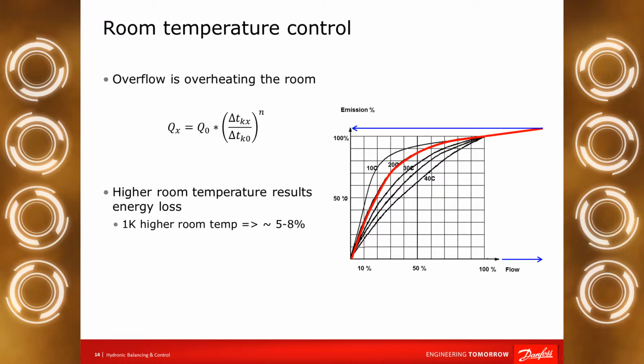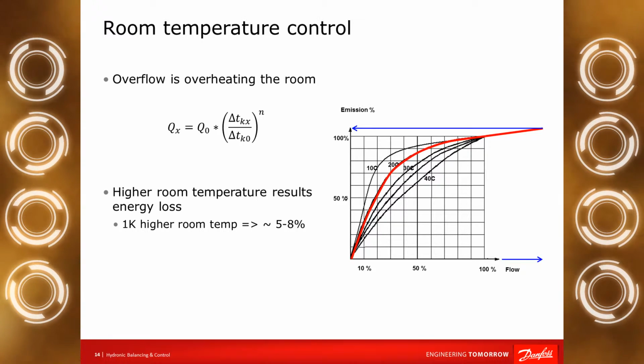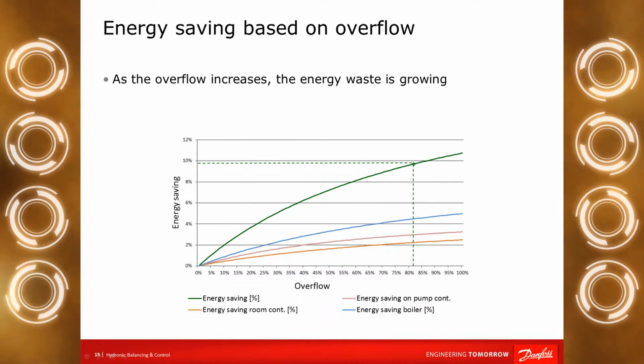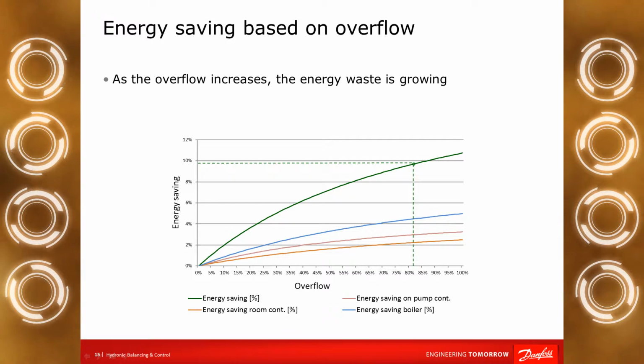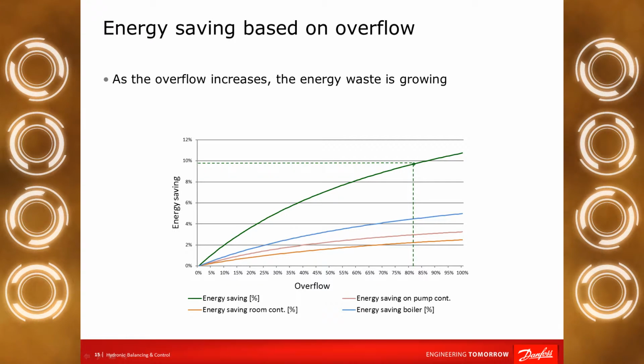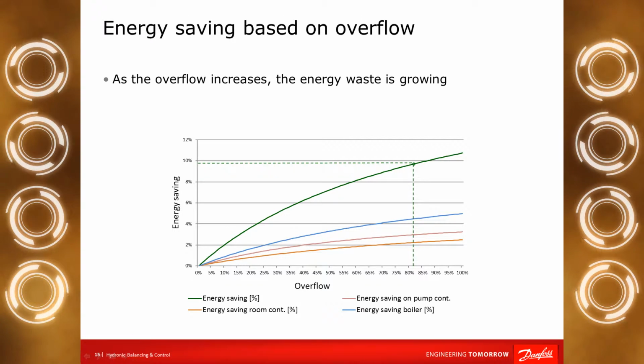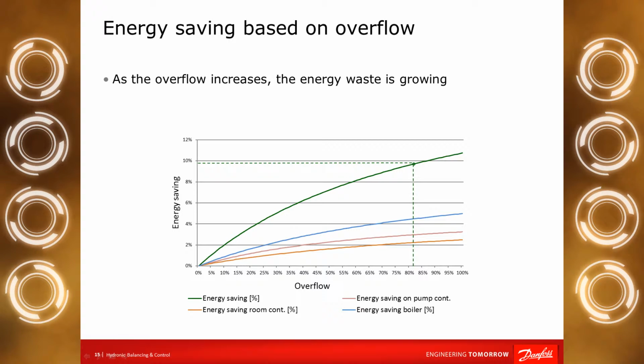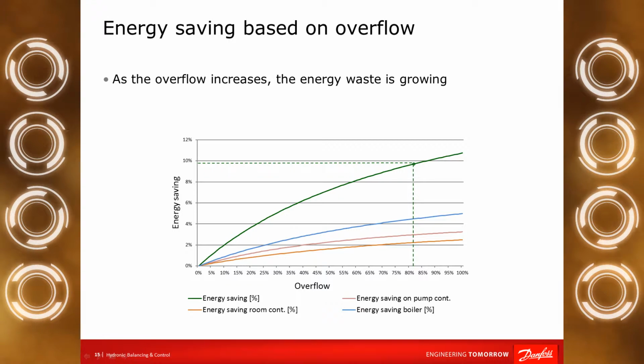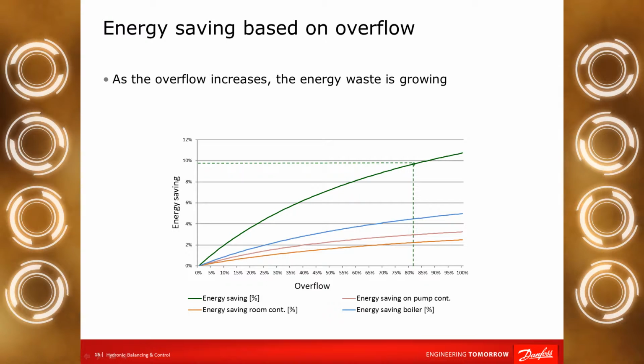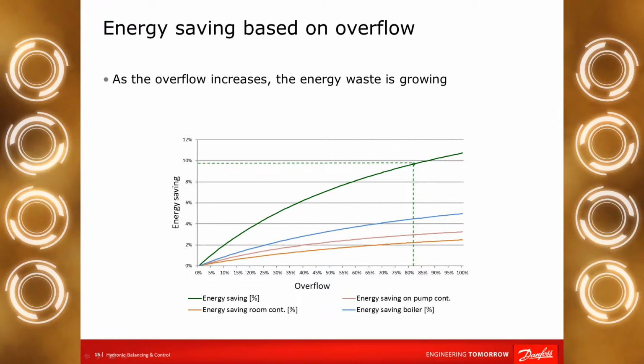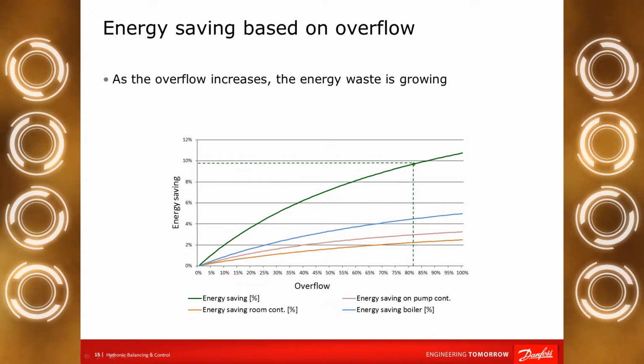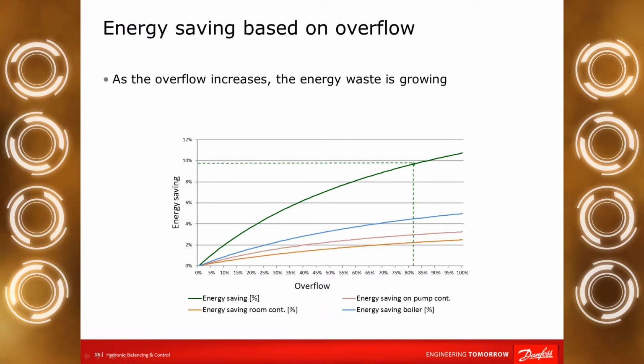plant. If we add these 3 parts together, we can get the characteristic of the overconsumption based on the overflow in the system. If you remember, I talked about around 80% overflow in a manual balance system. You can see, based on the calculation, it will result in around 10% over energy consumption.